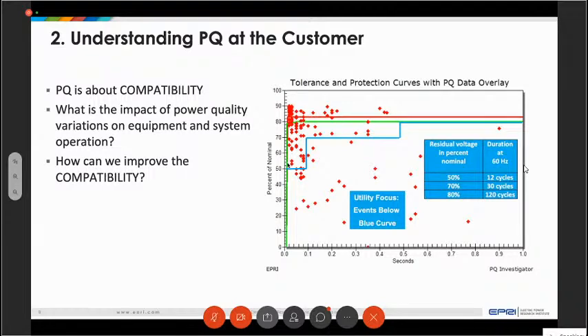So we like to say that we would like equipment to be able to operate properly even if the voltage goes down to 70% for half a second. That allows a lot of events caused by faults on the transmission system or on parallel distribution systems to be handled. The equipment doesn't misoperate for those events.